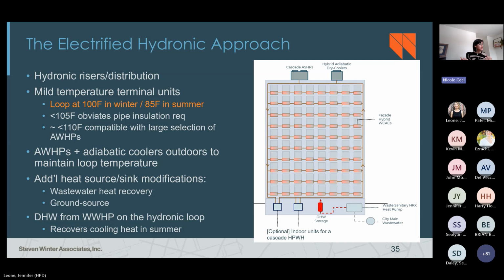And then lastly, domestic hot water. In the architecture as we tend to use it, we're typically getting domestic hot water from a water-to-water heat pump that is connected to that same building hydronic loop, if we're not picking up that DHW load from wastewater heat recovery or ground source. And producing domestic hot water off the loop lets us recover heat in the cooling season. And then in heating season, it does add load to the central plant.